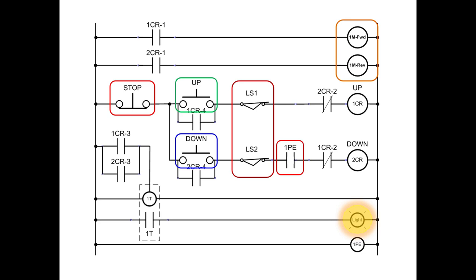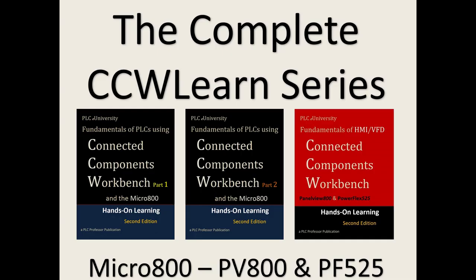Now if you want to consider how this circuit works, currently it's at rest and one of those two limit switches would have to be tripped. Now if the garage door is down, then LS2 is tripped and open. So you can't go down if it's already down. So if you press the up button, that has a complete path for current flow through 2CR-2 and that is a preventative for you trying to make it go up and down at the same time. And I'm not going to go through all this. You look it over and if you don't understand this electrical diagram, you better stop right here and spend some time considering it, otherwise the program won't make any sense when you write your program.